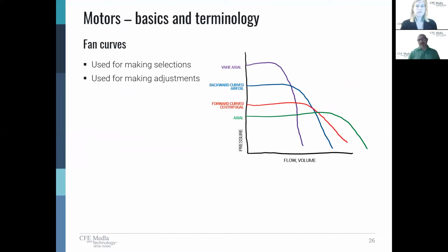An example of how to use that is with your fan curves. So we use fan curves to make selections. You can see here we've shown the relationship of pressure to air volume associated with a couple different types that I had previously talked about. Now, if you specify systems, you know fan curves pretty well. You know that they can include a bunch of other lines to tell you, well, this is the operating points. This is where they behave at different static pressures, how much power if I put into a certain type of fan. They're basically generated by the manufacturer and used by the engineer to make selections.